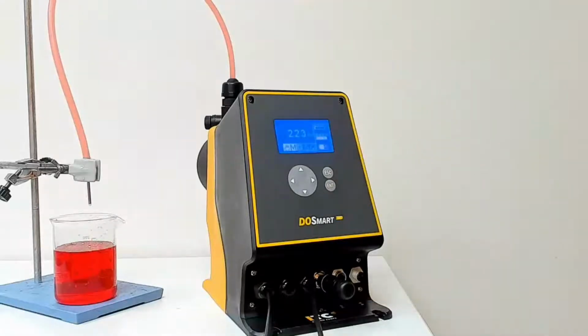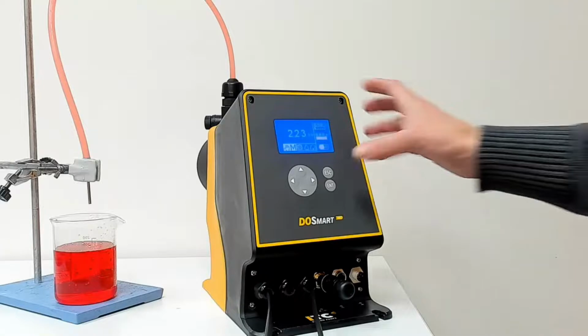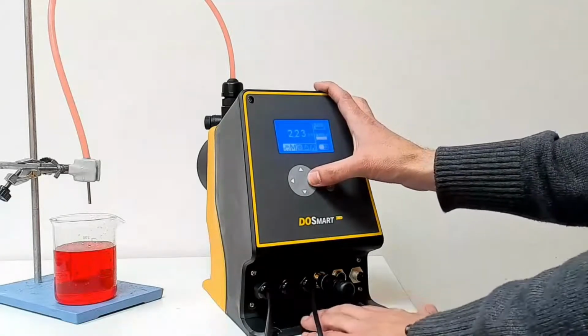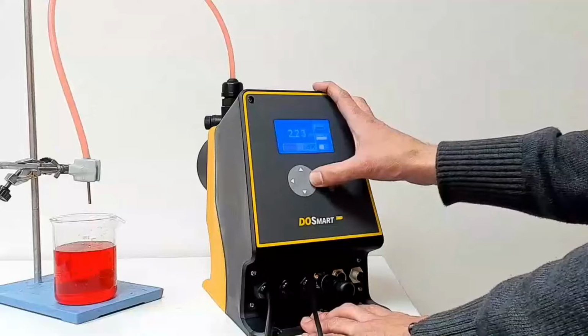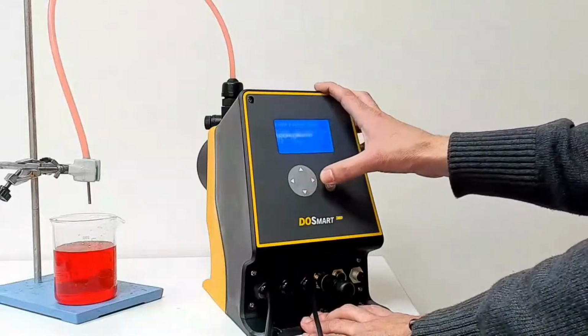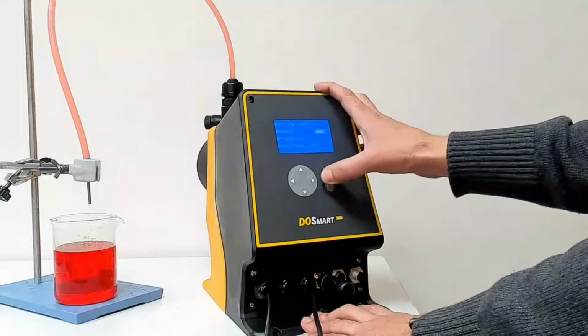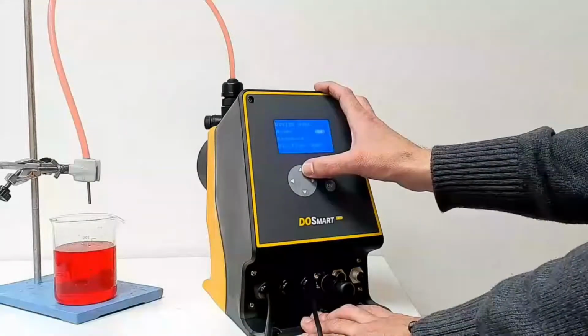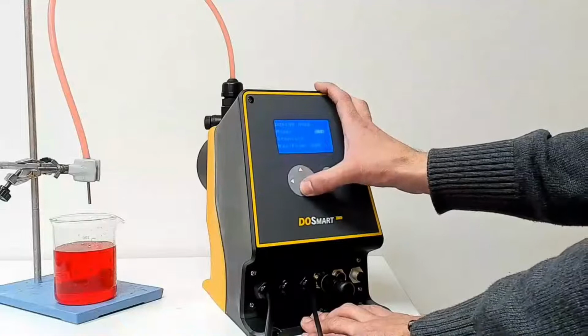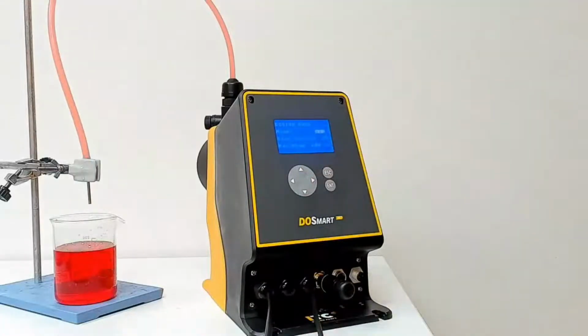For us, the suction cycle is very important, because if we don't fill the head completely, we won't have an accurate flow on the discharge side. So we need to ensure that the head is completely filled with product. And for this, we have the option that Alberto mentioned before, the special dosing modes, where we can choose from the standard, which is the one that we have already seen, and also the slow suction modes.